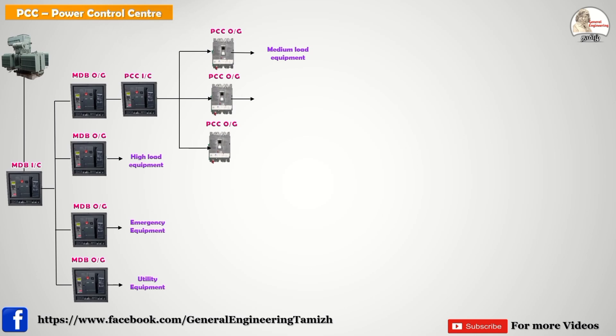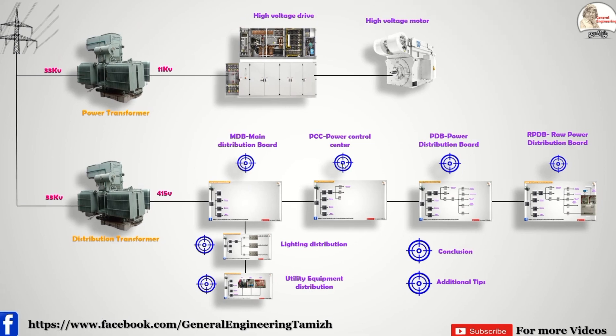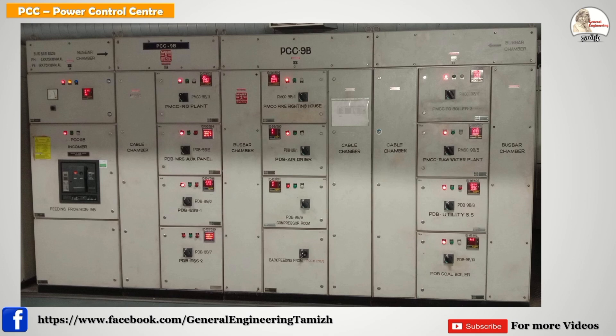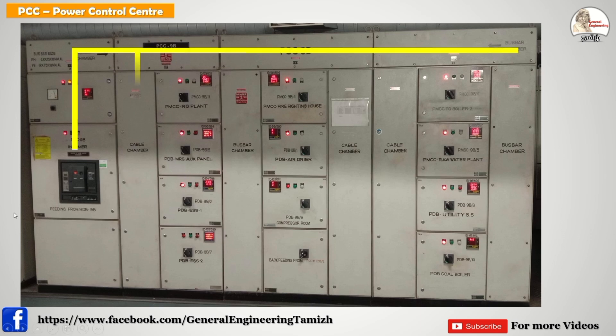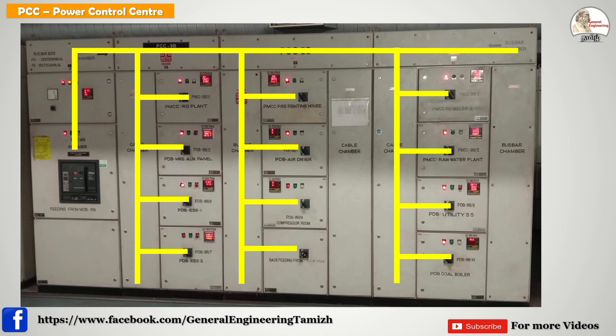Now let's move to panel identification. In the industry, when you see a panel, you have to differentiate which one is MDB and which one is PCC. This is the PCC panel — here you can see the Incomer Breaker, and its supply is coming from the MDB. The supply is distributed across the PCC panel via a bus bar connected to all outgoing feeders. The Incomer is an ACB and all outgoing feeders are MCCBs. From the MCCBs, all loads — medium kilowatt loads — are connected.